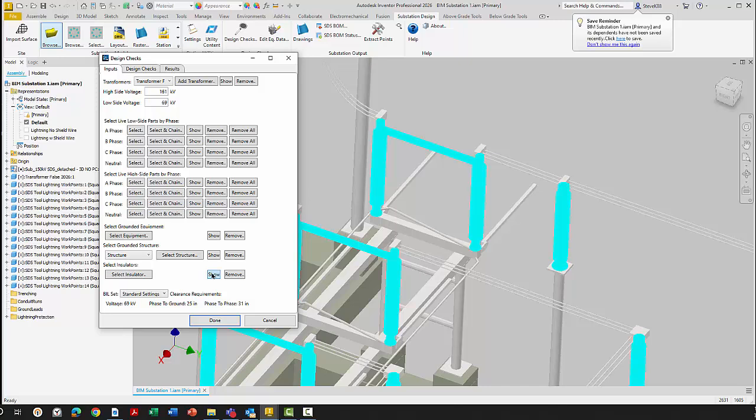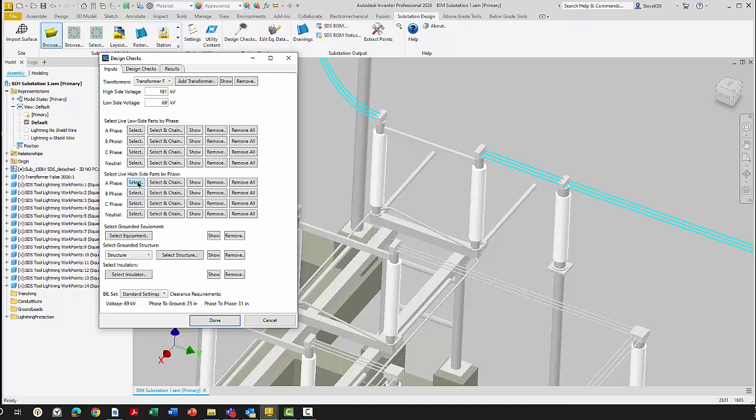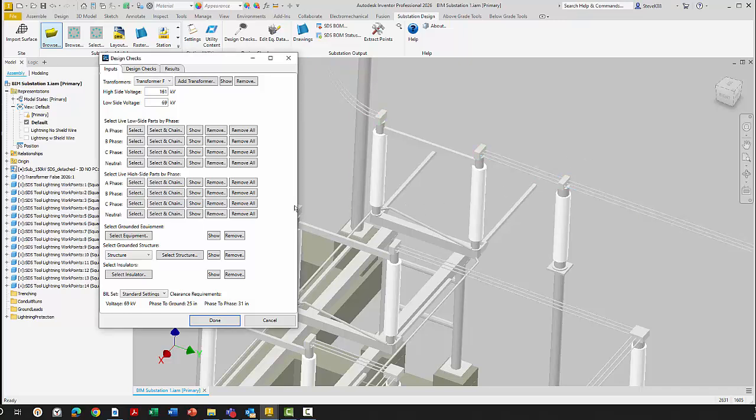We're going to run our design checks for phase to ground in this manner. The design of the equipment should pass because it was designed to pass for the voltage that it's rated for. When I come up to the phasing, you can see the phasing is coming down with the wires down to this point. So the cabling is coming down in here. That needs to be selected for each one. If I wanted to select these fittings, these fittings are just blocks here. I would come up here and hit select - select the block, select the block, and the block, and escape. And now that phasing is selected.